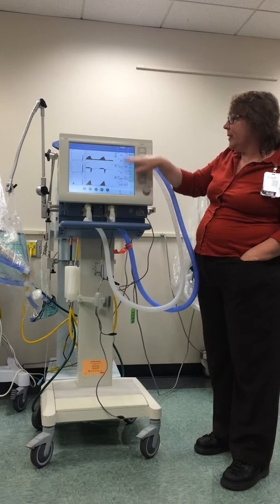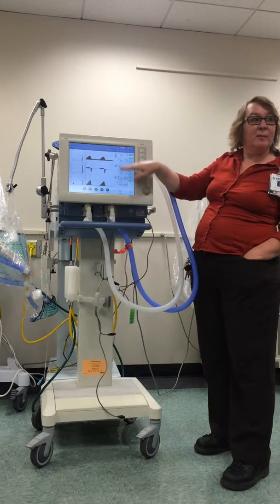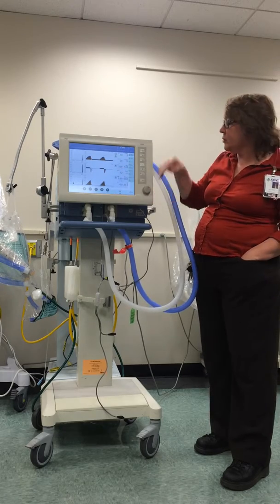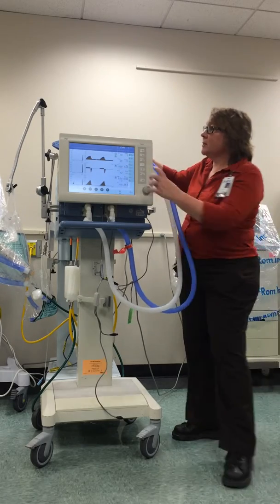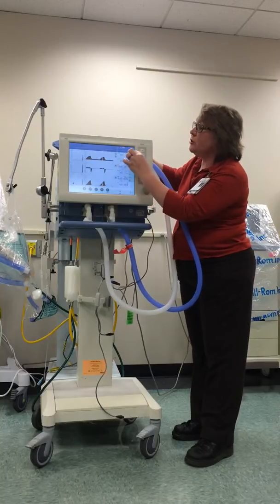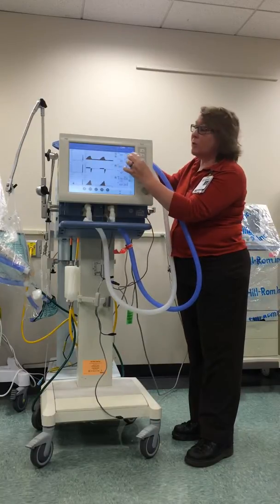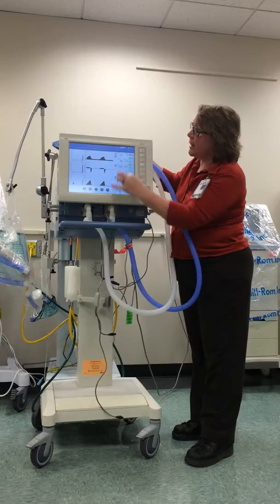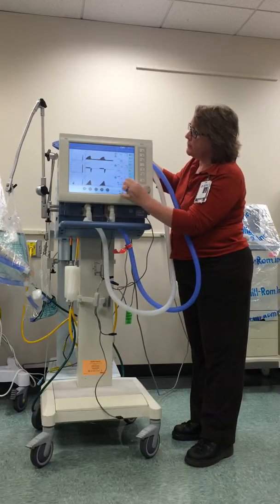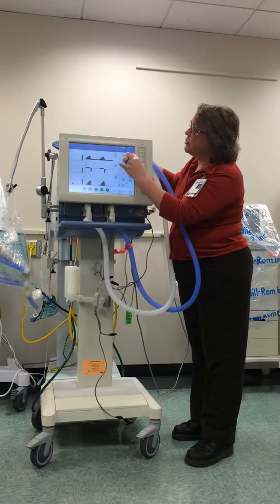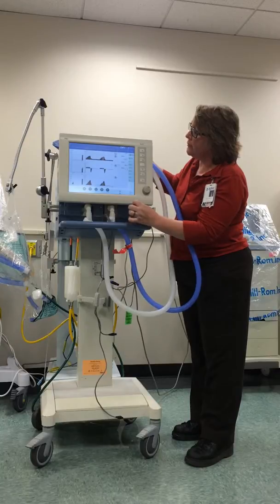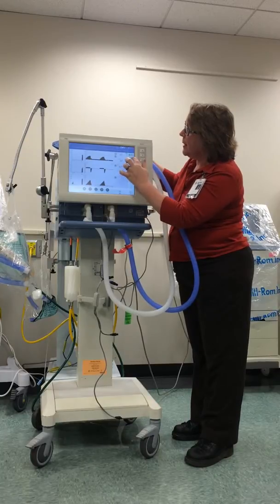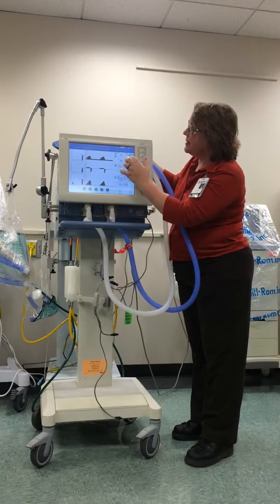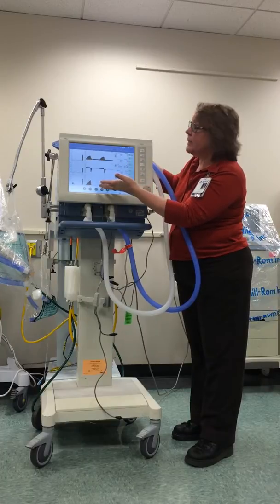So here is my patient data. So I can do my patient parameters check on my vent screen, on my vent check. There's a little tab here that says 1, 2, 3 up here in the upper right hand corner. So if I hit that, it'll change the data to more different ones. So you get different numbers. So you just go through the tabs till you find what you're looking for. Main would just take me back to this screen if I wasn't on it already.